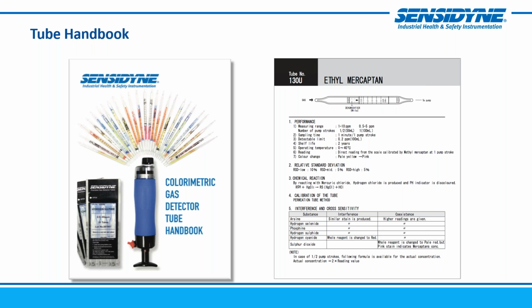One of the things I also want to point out is that these instruction sheets tell you about interference and cross sensitivities. This is important to know: not only what the result is, but whether my result is being impacted by other chemical gases that may be present. This also applies similarly with electrochemical sensors. If you were using a handheld monitor, even in areas like confined spaces, and there were interfering gases or cross sensitivities present, you may want to get a gas detector tube that would detect that interfering or cross-sensitive compound.